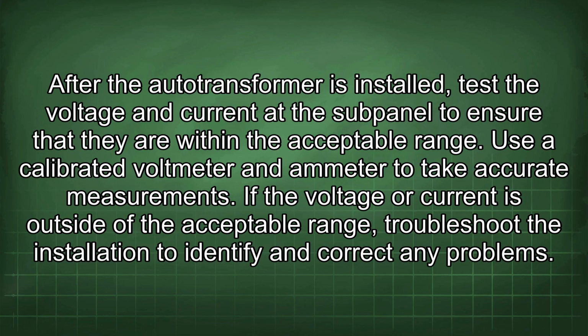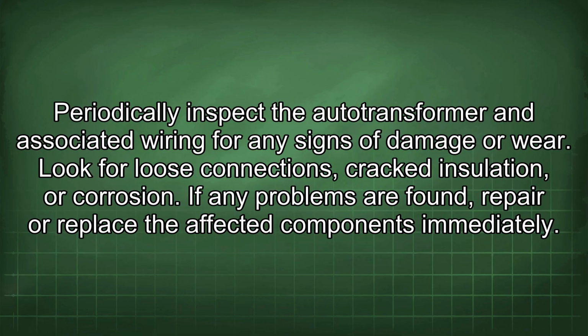After the autotransformer is installed, test the voltage and current at the subpanel to ensure that they are within the acceptable range. Use a calibrated voltmeter and ammeter to take accurate measurements. If the voltage or current is outside of the acceptable range, troubleshoot the installation to identify and correct any problems. Periodically inspect the autotransformer and associated wiring for any signs of damage or wear. Look for loose connections, cracked insulation, or corrosion. If any problems are found, repair or replace the affected components immediately.